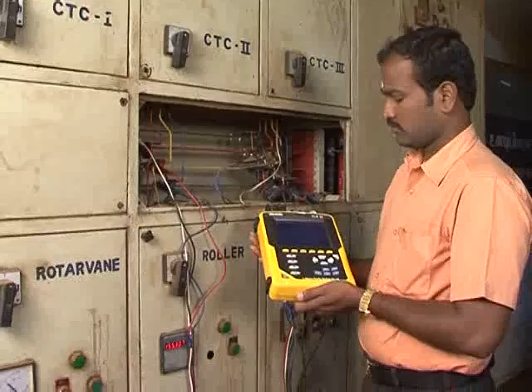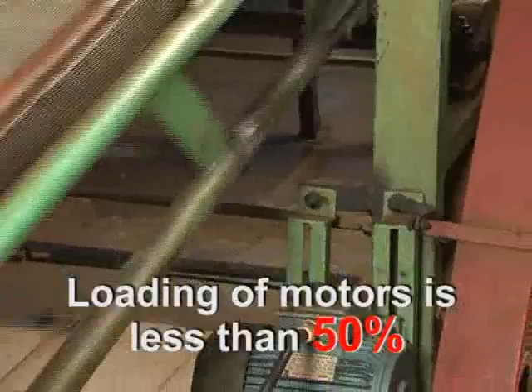After knowing the exact energy requirements, there are two ways to reduce energy consumption: downsizing of the motor. If the percentage loading of motors is less than 50%, that is maximum load, they need to be downsized.